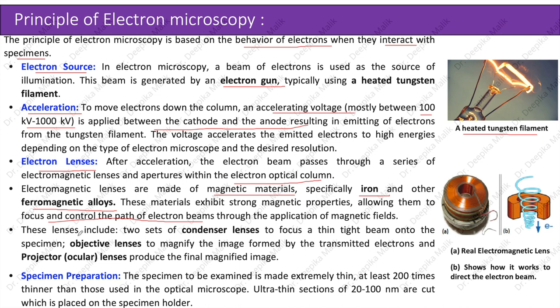These lenses include two sets of condenser lenses to focus a thin tight beam onto the specimen, objective lenses to magnify the image formed by the transmitted electrons, and projector or ocular lenses to produce the final magnified image. Here you can see the real electromagnetic lens; the second image shows how it works to direct the electron beam.